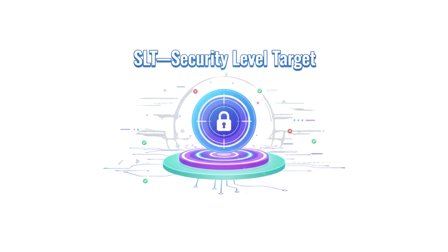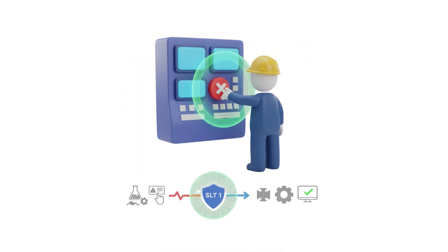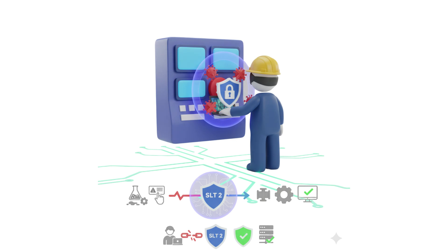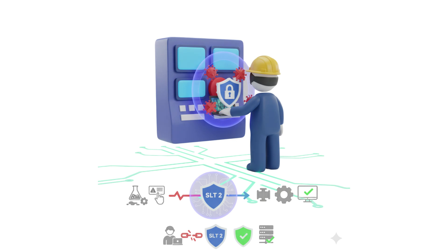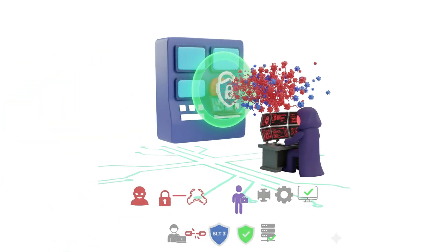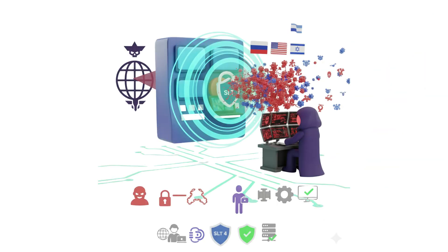One of the most important concepts in IEC 62443 is SLT — Security Level Target — a measure of how secure a system needs to be. There are four levels: SLT 1 protects against accidental or casual violations, such as preventing operator mistakes. SLT 2 defends against intentional but low-skilled attacks, such as blocking basic malware or phishing. SLT 3 provides resilience to sophisticated planned cyber attacks, such as ransomware or insider threats. SLT 4 is the highest security level, safeguarding against advanced persistent threats (APTs), such as nation-state cyber espionage.